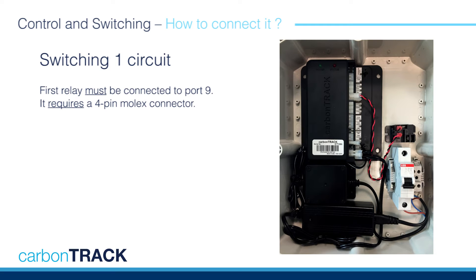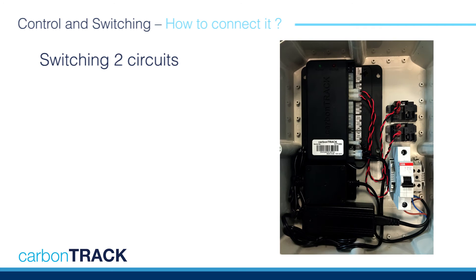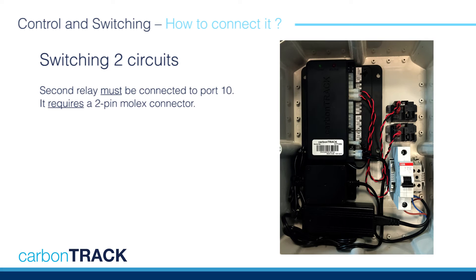you must connect the relay coil into port 9 of the CT100i using the 4-pin Molex connector cable. When switching two circuits or loads, the second relay coil must be connected into port 10 of the CT100i using a 2-pin Molex connector cable.